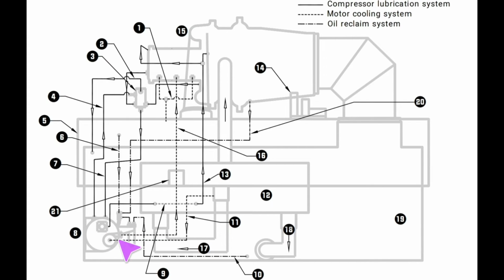So we'll dive a little bit deeper into that, but we'll finish specifically all the refrigeration side of the circuit, and then we'll talk a little bit about the oil management and just kind of how that plays a factor. So like I was discussing earlier, right here is that drain coming back into the condenser for the refrigerant after it has finished cooling the motor. That is being fed from down here. So coming off of the liquid line right here into this little assembly here at the sump. This is actually a refrigerant pump that is tied to the mechanical oil pump inside of the oil sump.